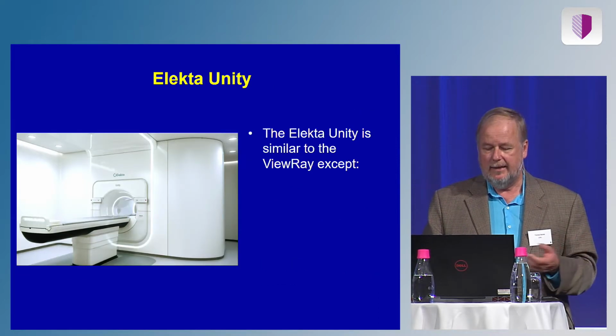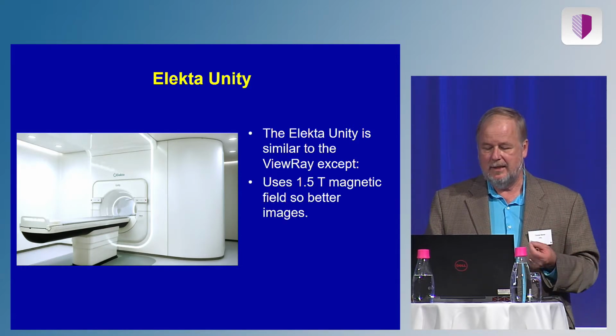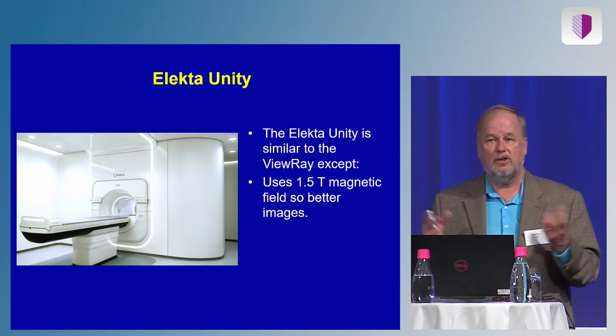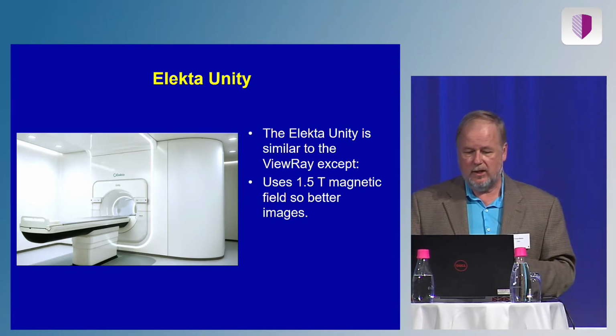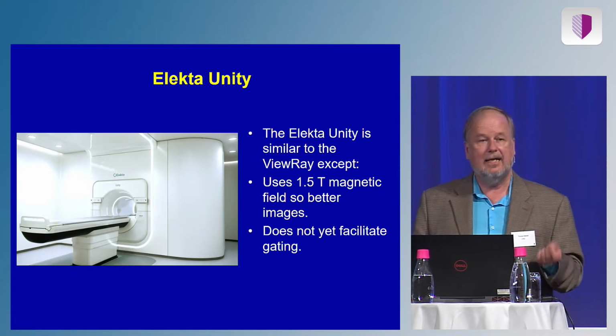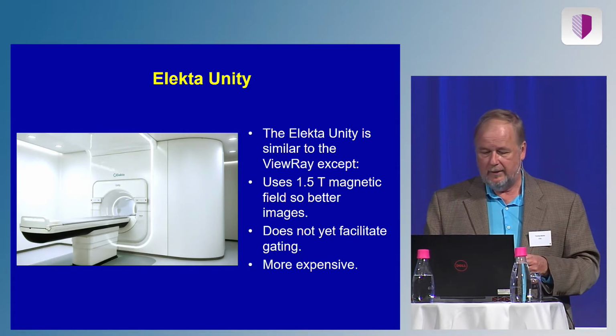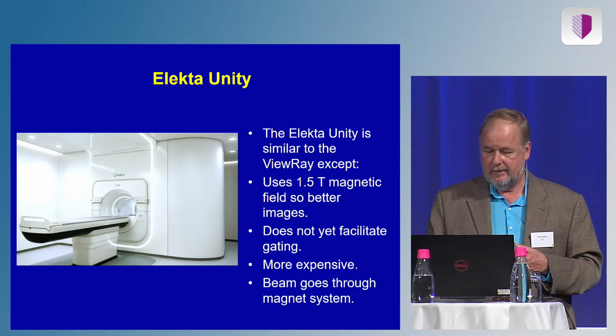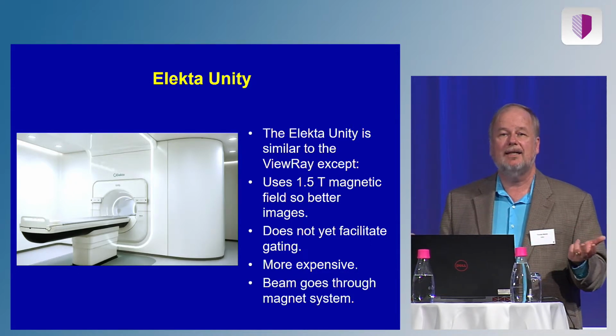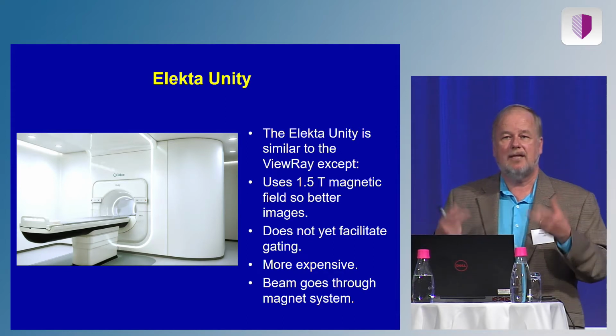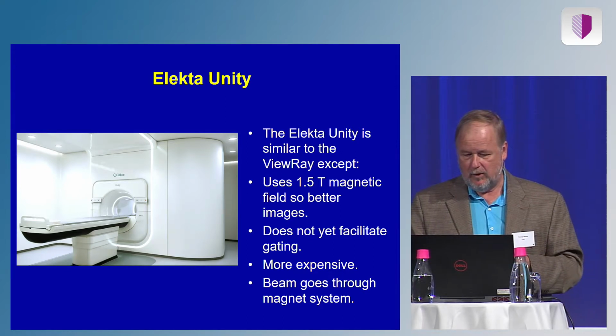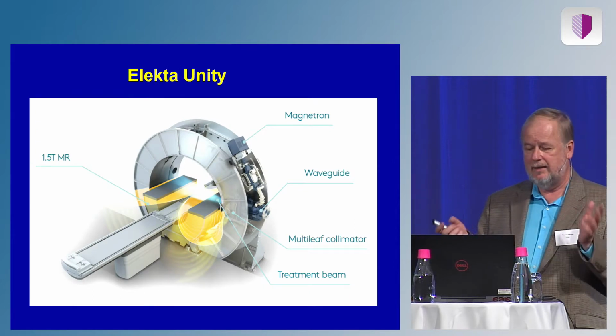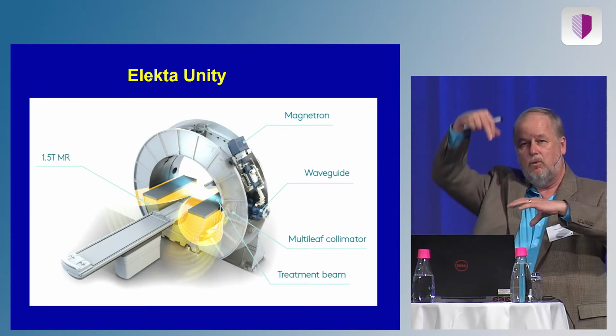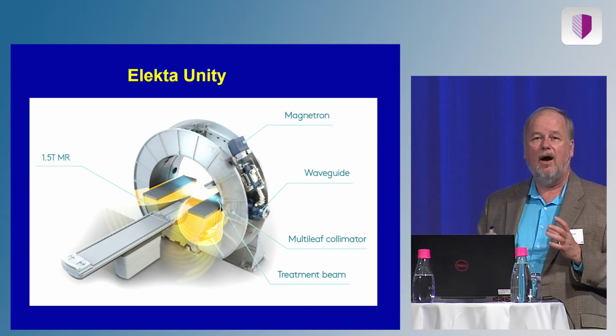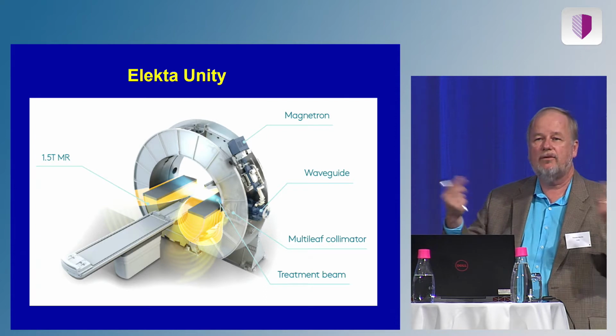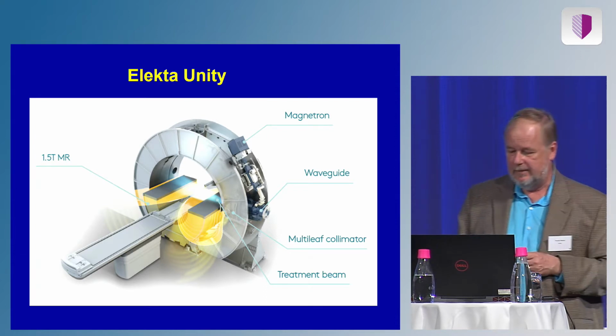The Elekta Unity is similar to the ViewRay, except it does have a higher quality imaging. It's 1.5 T, which is a diagnostic quality. It doesn't yet facilitate gating, but I'm sure it will. It's a lot more expensive. And the beam actually goes through the magnet system. They haven't left a gap. So there is some scatter coming from the patient to worry about. And this is actually a view. The Elekta Unity is a magnificent machine. It basically is irradiating through an MR. The LINAC is on the outside, irradiating through a more or less conventional Philips MR system.